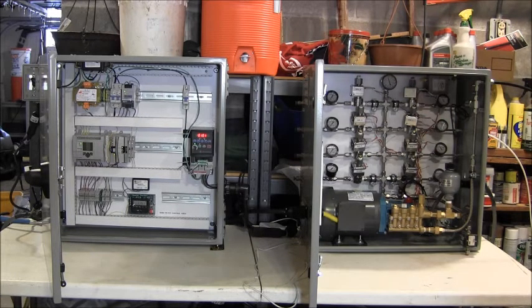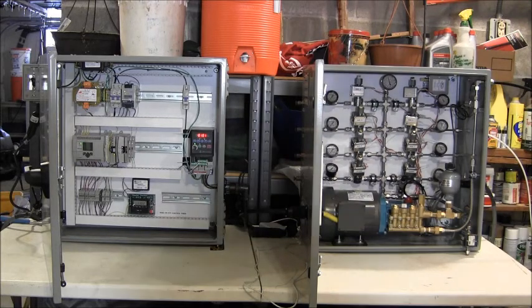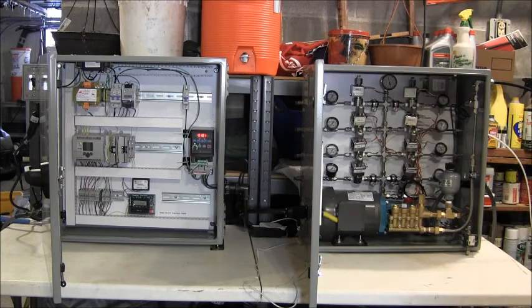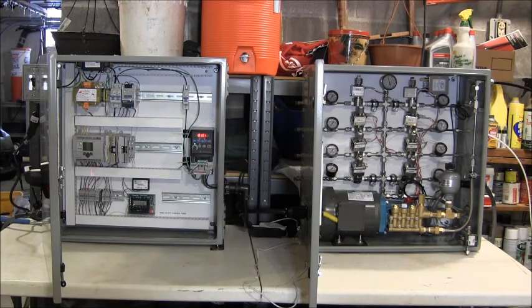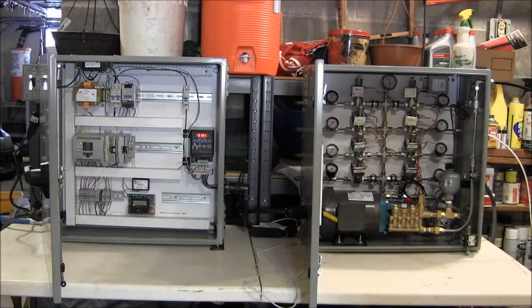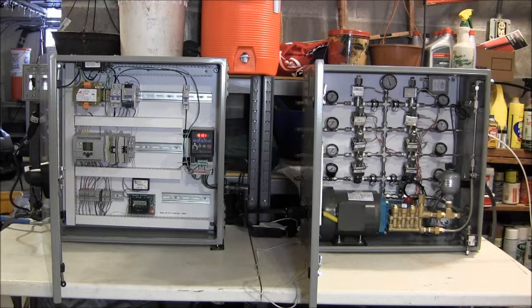So these are two separate units. We've got a control panel and we've got a pump panel, a pump package. There are two cable assemblies. I showed one to you a little earlier that connect the two together. So they are shipped separately. The cables are inside each one of the control panels. There is one for the variable frequency drive, coming out of the VFD and going into the motor. The other one is the control cable. That's down here on the lower left, just below the disconnect, and its incoming connection is right there, and that goes over to the pump package on the far right. There is a connection right there. That's a 12-foot cable. Both of them are 12-foot cables that interconnect the two panels.